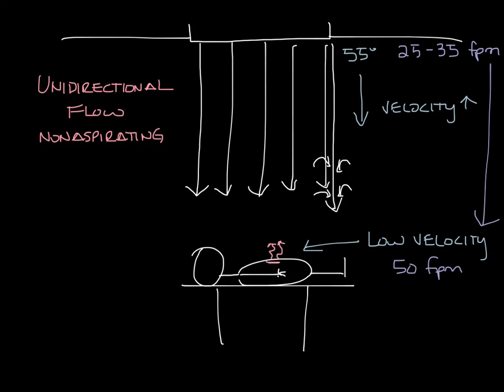A 2002 NIH study found that the thermal plume rising from the surgical site was enough to keep the surgical site clean, as long as the airflow velocity was low enough that it didn't overcome the thermal plume. They found that 25 to 35 feet per minute at the diffuser face was sufficient to make this happen.